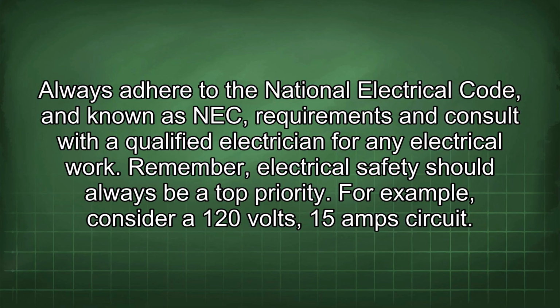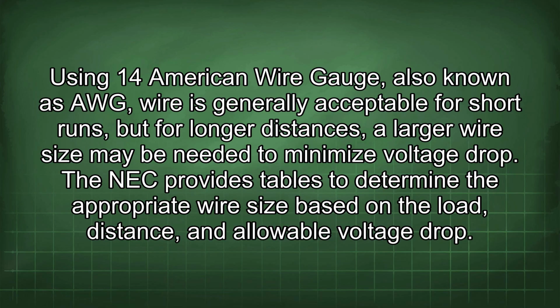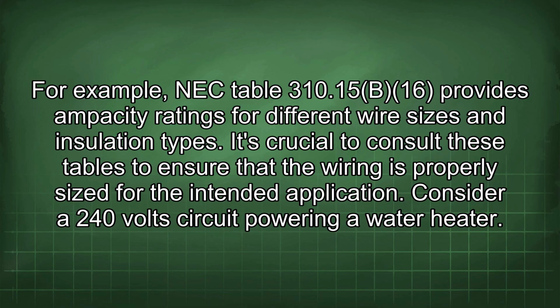For example, consider a 120 volt, 15 amp circuit. Using 14 American wire gauge, also known as AWG, wire is generally acceptable for short runs, but for longer distances, a larger wire size may be needed to minimize voltage drop. The NEC provides tables to determine the appropriate wire size based on the load, distance, and allowable voltage drop. For example, NEC Table 310.15(B)(16) provides ampacity ratings for different wire sizes and insulation types. It's crucial to consult these tables to ensure that the wiring is properly sized for the intended application.